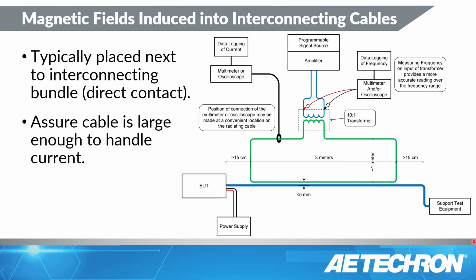The problem with that is if the group has created your cable and they made it a little bit too short, you can't expose 3 meters of wire and maintain this 15 centimeters. You may find that your exposed wire has to drop down by a certain factor, 2.8, 2.5, maybe even, let's say 2 meters. You only have 2 meters of exposed cable. Well, if you can only expose 2 meters, then instead of 40 amps in that cable, you're going to have to bump it up 33%, well, actually, you have to bump it up to 60 amps of current. And that's the reason why we want to use a very high current carrying cable.